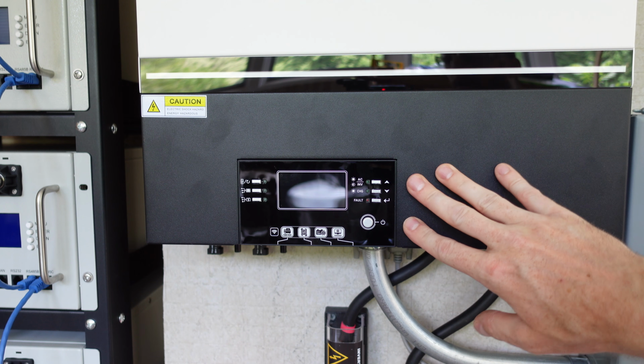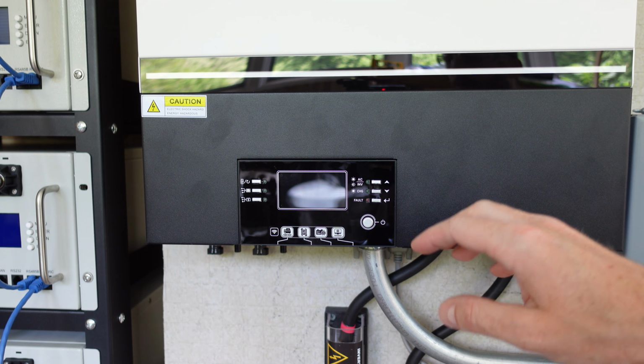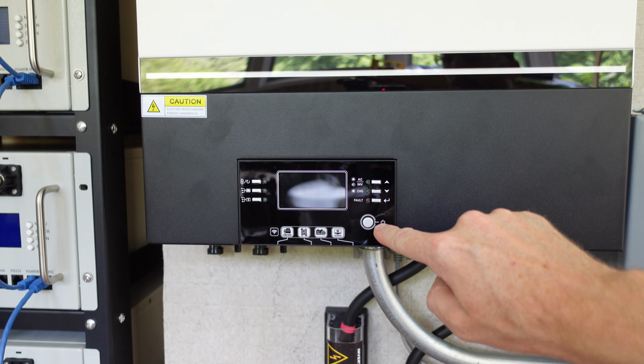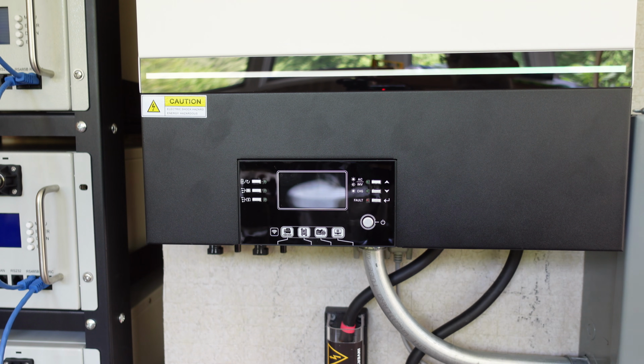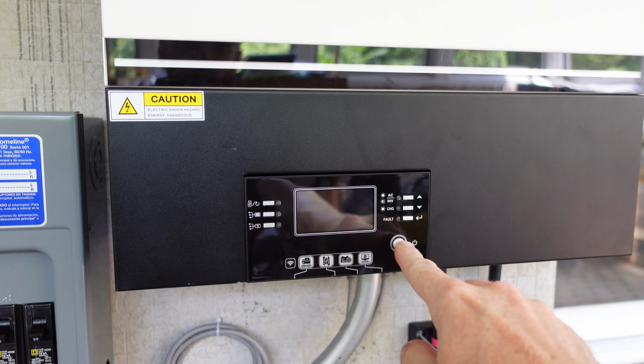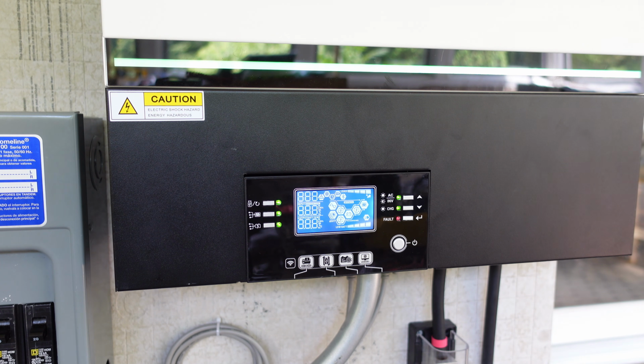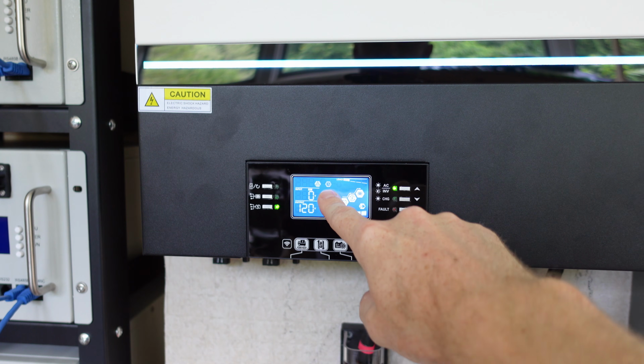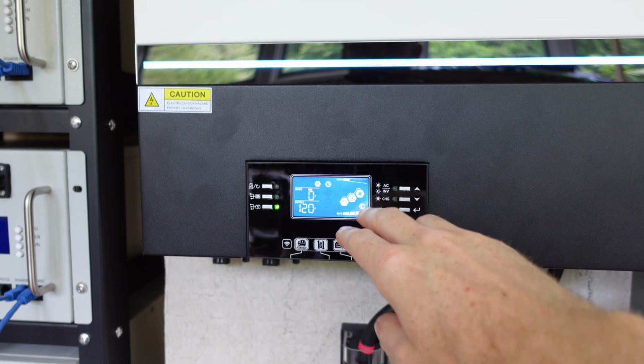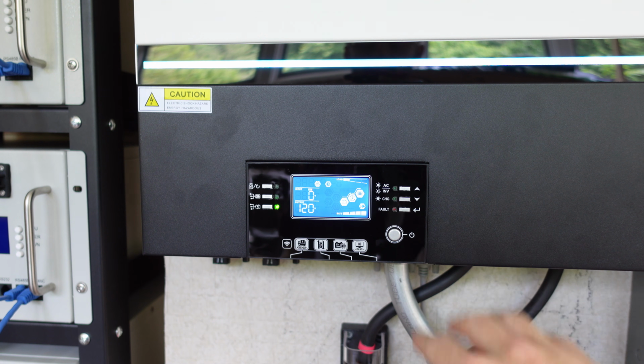So I'm going to start up each one of these inverters, and then we need to tell it to operate in split phase mode. Go ahead and push the power button. And this one as well. Alright, so I do see there's a warning light flashing on this inverter. I haven't looked into it too much yet because we need to tell these inverters to communicate first, and that may be why it's complaining.